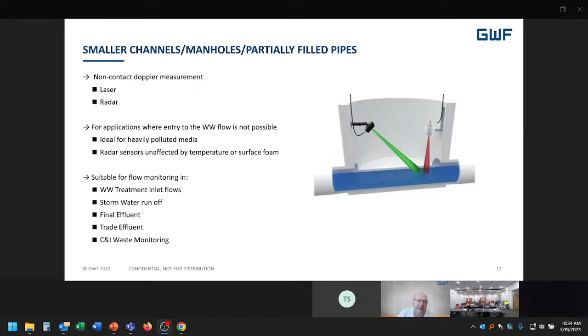Now, how do these measure? In reality, these are measuring a point. On the right here, you'll see a graph of a channel. When you're measuring at a point, we're showing some dots that relate to the point where it's measuring. If you just measure that point and convert that, assuming everything's flowing at the same rate, you'll be quite wrong.